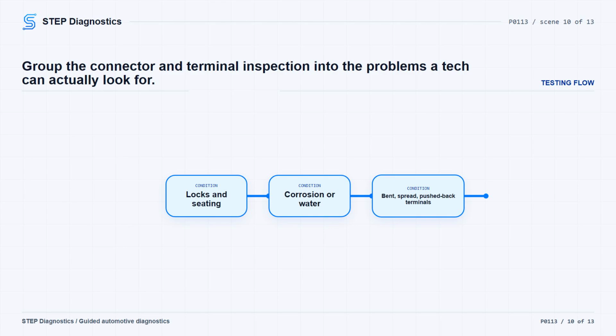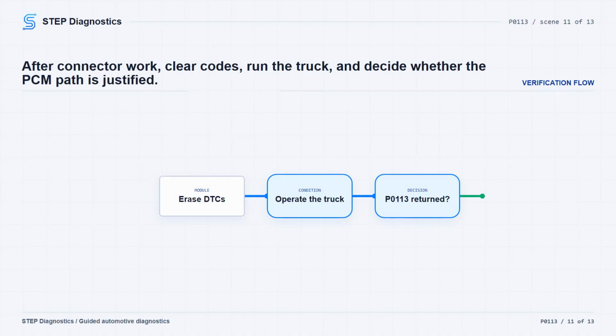Disconnect all PCM harness connectors, any related inline harness connections if equipped, and the related component connectors. Inspect the harness and component connectors, along with the male and female terminals, for installation problems, damaged locks, corrosion, water intrusion, seal damage if equipped, bent terminals, signs of overheating from a poor connection, terminals pushed back in the cavity, spread terminals, and poor terminal tension.